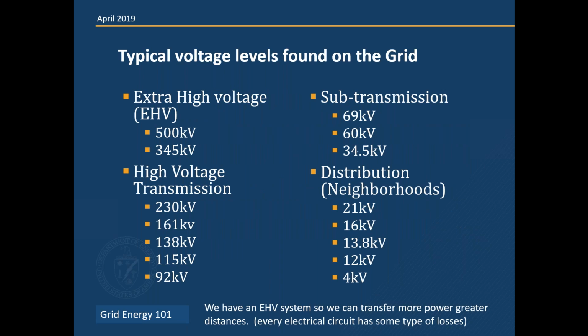So here's some typical voltage levels that you'll find on the grid. Let's start at the top. We have the extra high voltage. Here in the Western Interconnection, our EHV system is 500 kV and some 345 kV. I know that in the Eastern Interconnection, they have some 765 kV. The reason we have an extra high voltage system is so we can transfer more power greater distances. Every electrical circuit has some type of loss, and to help minimize those losses, we have to crank up the voltage to a higher level. And because power plants traditionally are a long ways away from the end use customer.